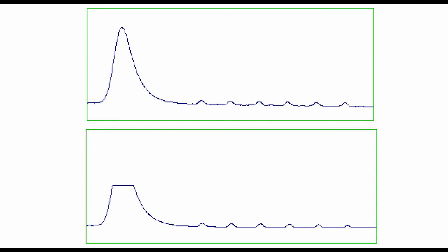When the top of the peak is cut off, it looks much like an overloaded detector. However, close examination reveals that the trace is absolutely flat and free of noise when it hits the limit. Furthermore, the limits are sharp and always at the same voltages, which are characteristic of the digital-to-analog converter. By contrast, upon magnification, a trace produced by an overloaded detector still shows some noise, and the limit is soft. A solvent peak that runs into the upper limit is not always a problem since it is not quantified anyway. A baseline that runs into the lower limit is always a problem.